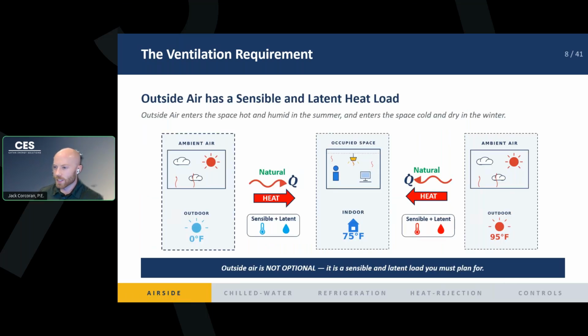Right, so we're bringing in all this outside air for code reasons, makeup air reasons, mass balance, and it's required, but it also carries a heat load with it, right? Our occupied space is in the middle of the screen here. It's our 70 to 75 degrees Fahrenheit. If you're bringing in outside air, unless it's exactly 75 or in that range, you're going to be adding a heat load to the space, right? If you have on the left side a very cold winter day at 0 degrees in New York, we know it can definitely get to 0 degrees. You have a lot of cold air coming into your building that you'll have to heat up, right? You have to spend energy to heat that air up, and you're also bringing in all that dry air, which may have negative consequences if your space can't be super dry.